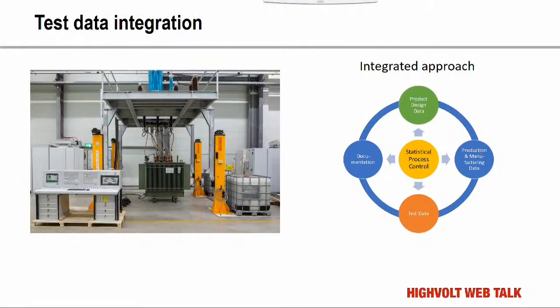In general, it's like collecting tons of data during the measurement of your test. If we're talking about distribution transformers, we have the measurement of the no-load losses, the induced voltage, partial discharge measurement, and so on. Even with the partial discharge measurement, you have a criteria, maybe 10 picocoulomb, so finally the result of the test is that the transformer is okay if the value is below 10 picocoulomb, or it is higher and then you have to repair it. Nevertheless, the collected data are much wider and bigger - you have PD patterns during the measurement, and that gives you more information than just the criteria okay or not.